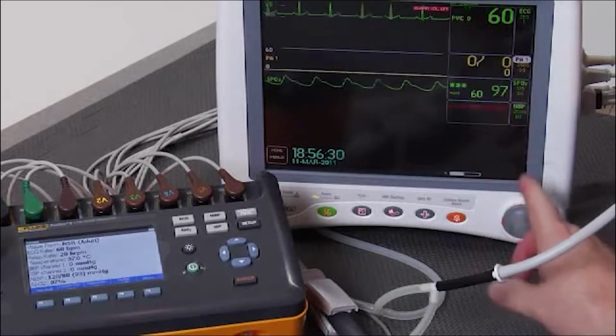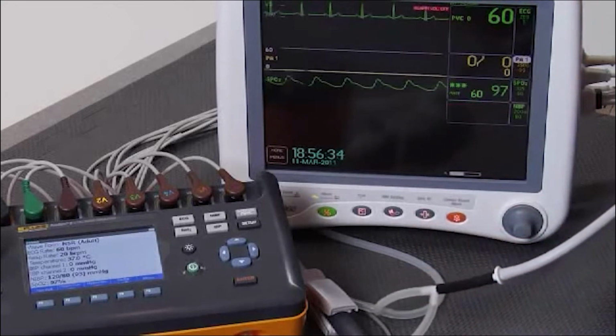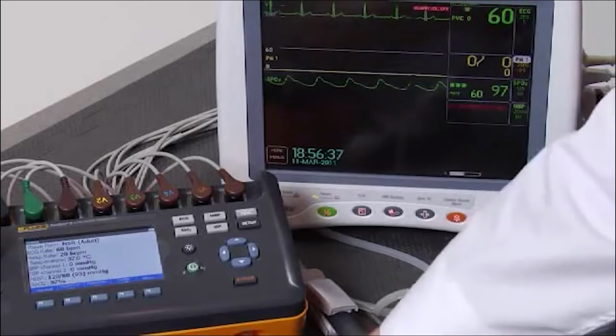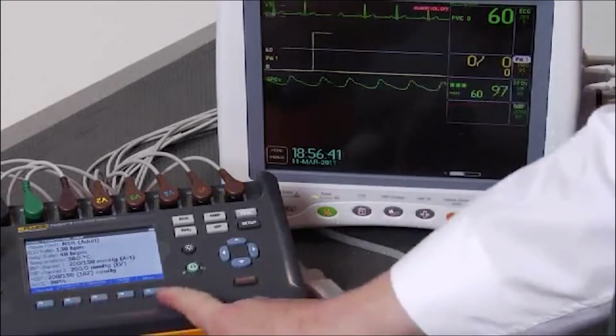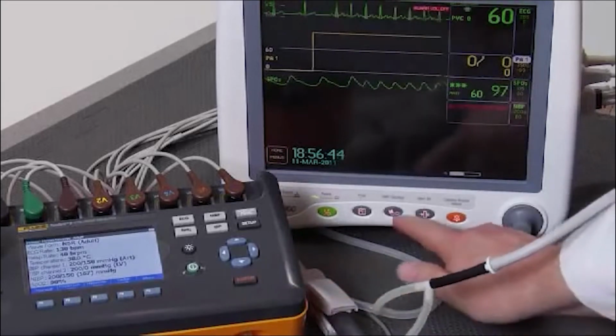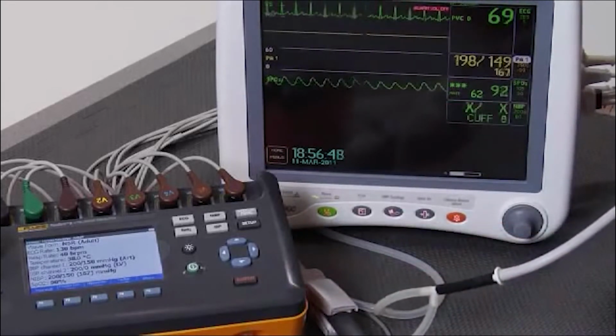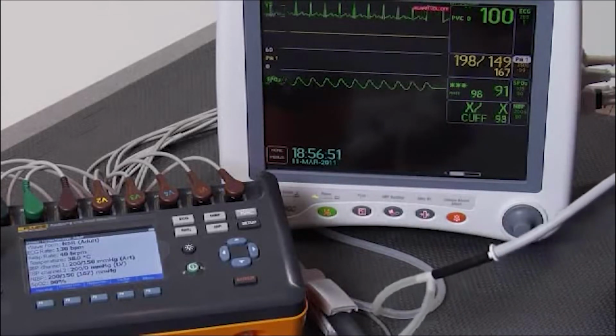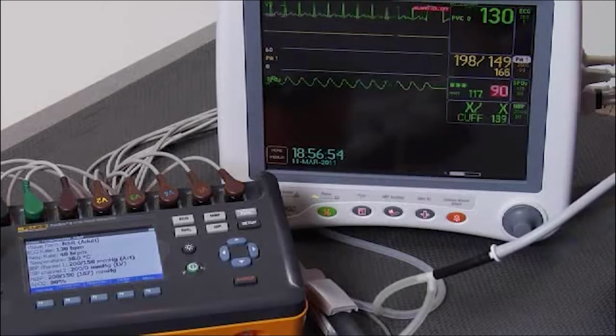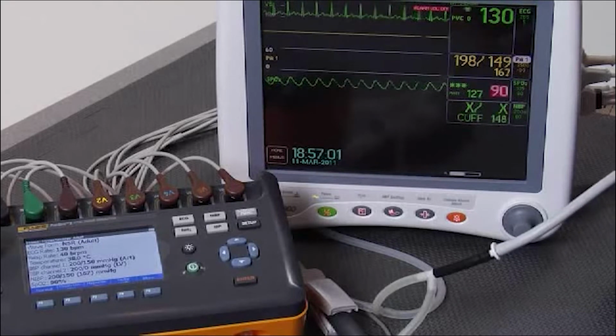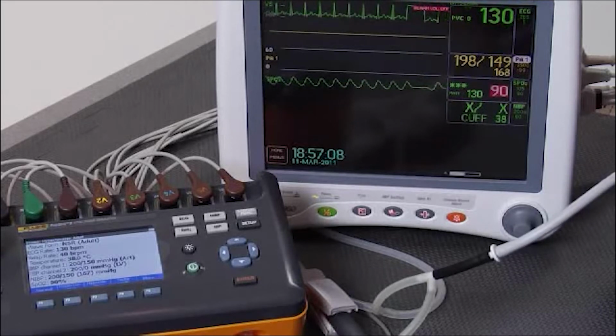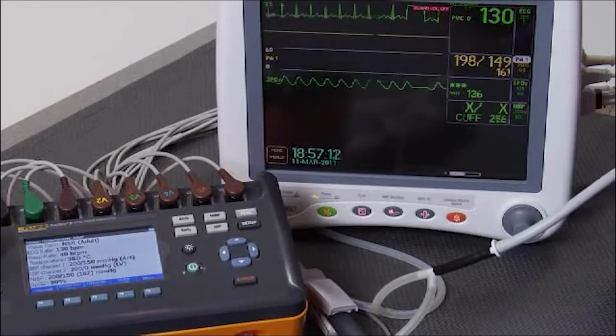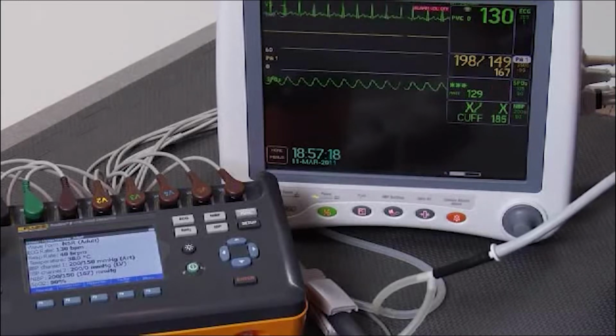now. First thing I'm going to do is zero P1. It is at 0. And now what I'm going to do is pick hypertensive. And the simulation will already begin, so I'm going to start a cuff blood pressure reading. In this case, we're looking for an ECG rate of 130 beats per minute, respiratory rate of 40. We're looking for an invasive blood pressure display of 200 over 150. We're looking for NIBP of 200 over 150 with a mean of 167, and an SpO2 reading of 90.